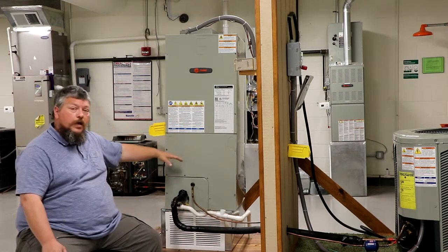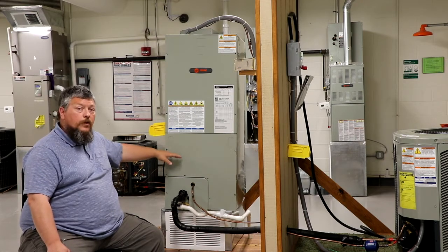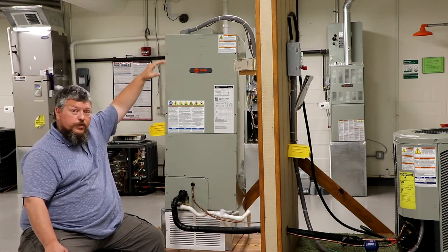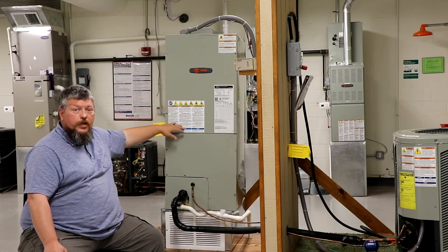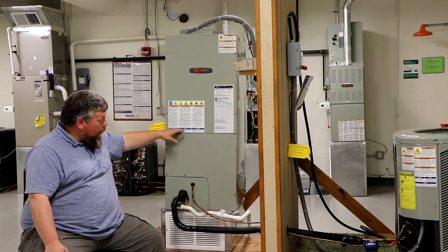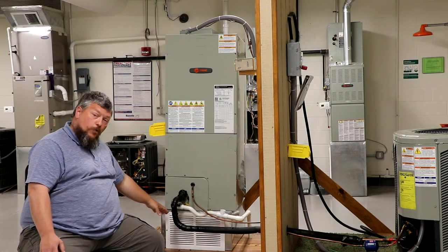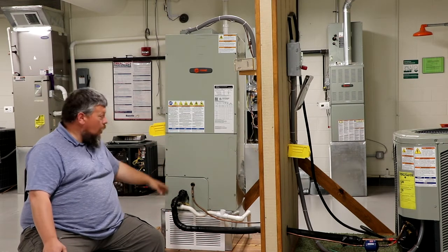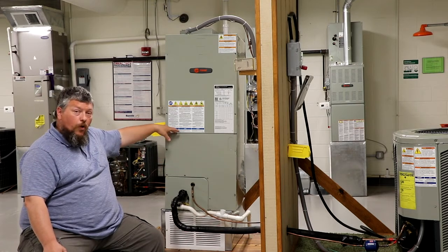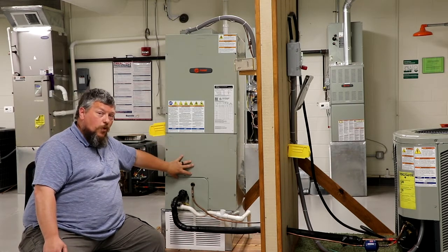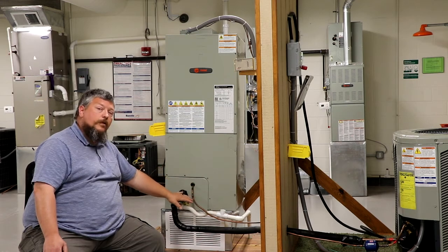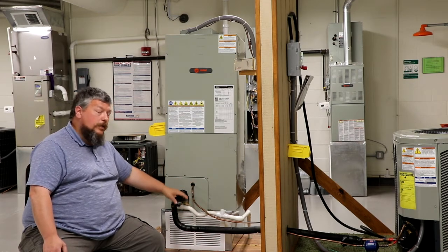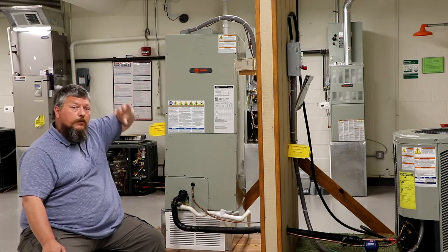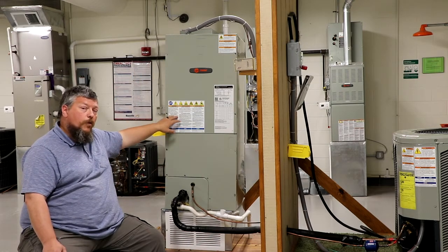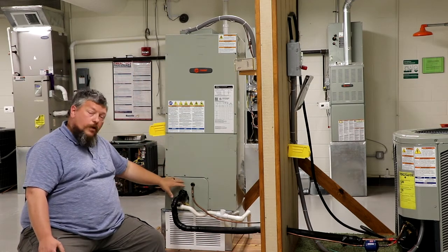This particular unit is what we call an upflow, so it will move the air upwards. There are others mounted in different configurations, but for this one, it pulls return air into the bottom, pulls that air over the coil where it absorbs heat into the refrigerant running through your refrigerant lines, and then that cooler air is pushed out into your home.